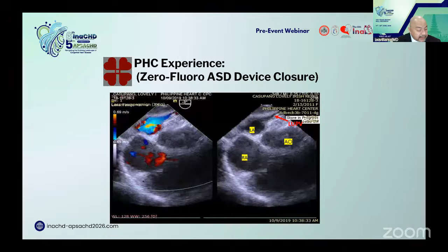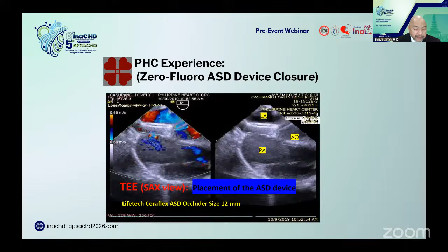This slide shows that the device used was a Ceraflex occluder, 12 millimeter, which is in place. The LA discs is at the left atrium and the RA disc is at the right atrium. Once the position is secured, our echocardiographer will make sure that there are no leaks at the sides of the device. The only leak that is admissible should be within the device.